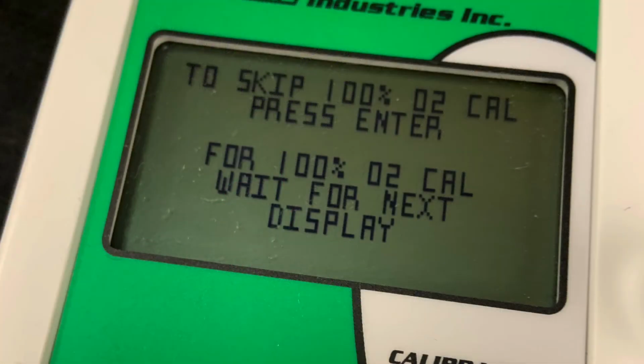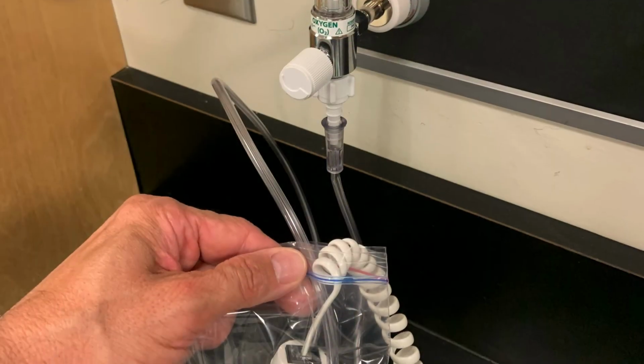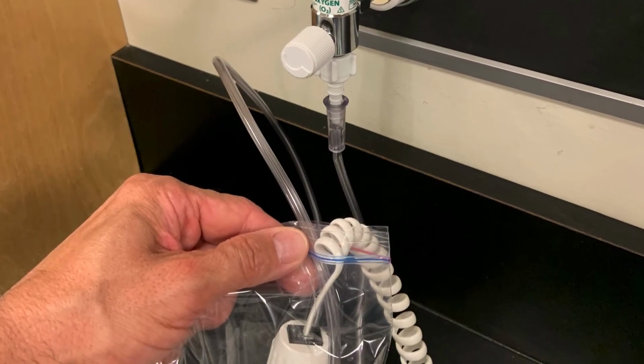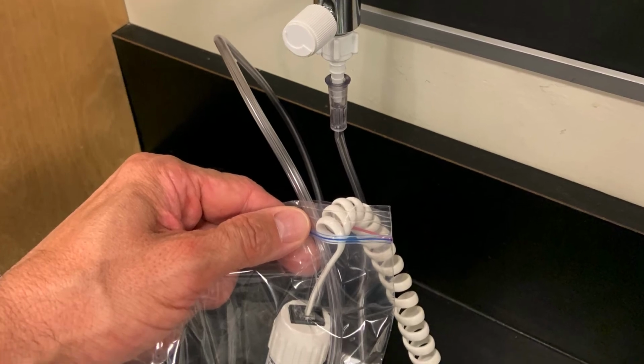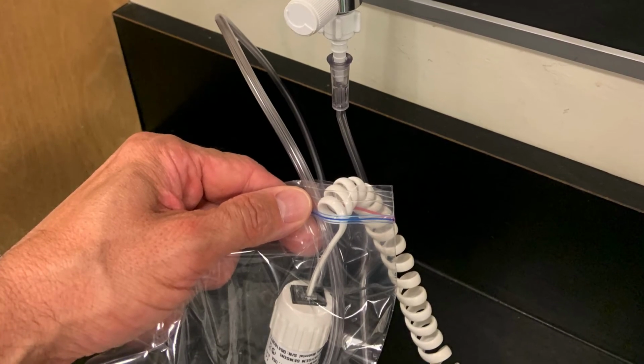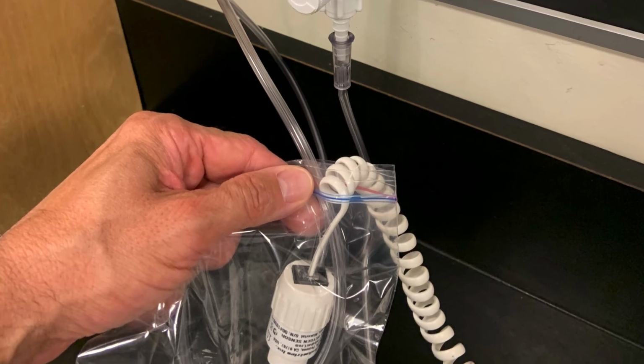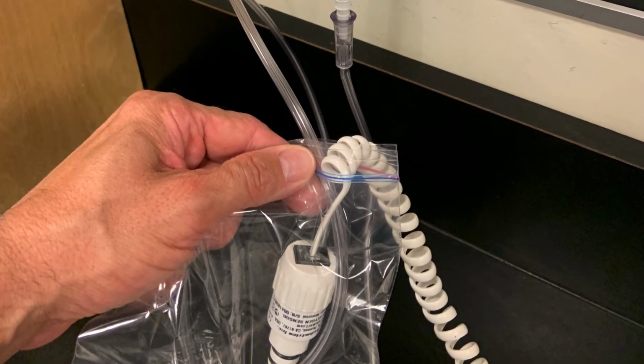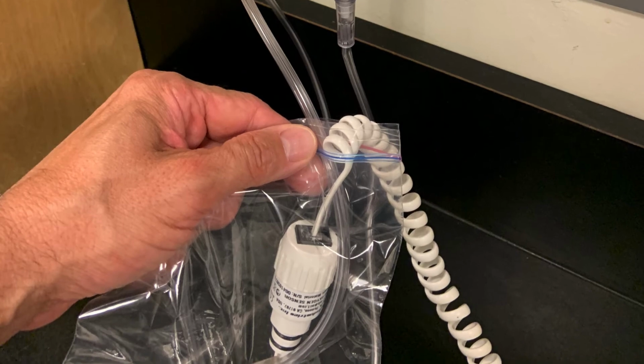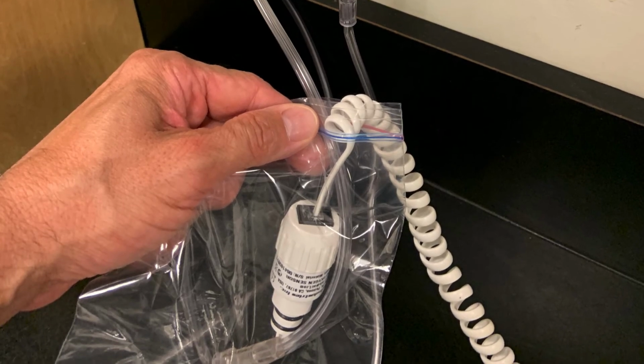Now that we've calibrated the analyzer to 21%, we should calibrate it to 100%, which is the high point cal. If you don't want to do that and you want to skip the high point cal, you press enter. But otherwise, if you just wait, it will lead you to the next calibration screen. Part of that is exposing the analyzer probe to 100% oxygen before you actually start the calibration process. So here I've placed the probe into a plastic bag with 100% oxygen flowing into it from an oxygen flow meter.